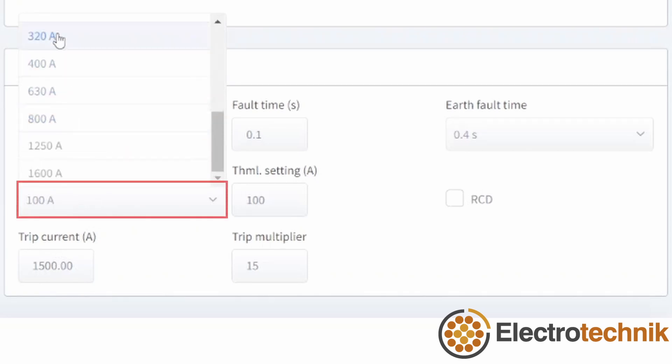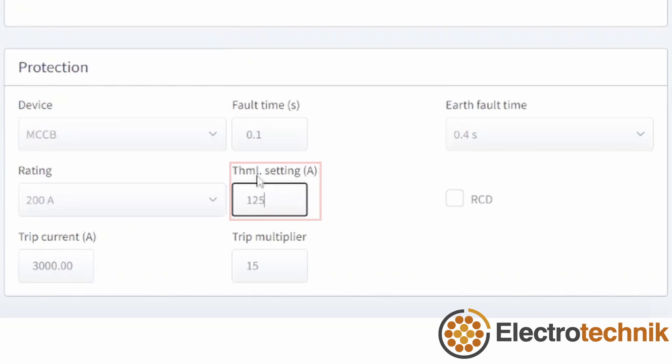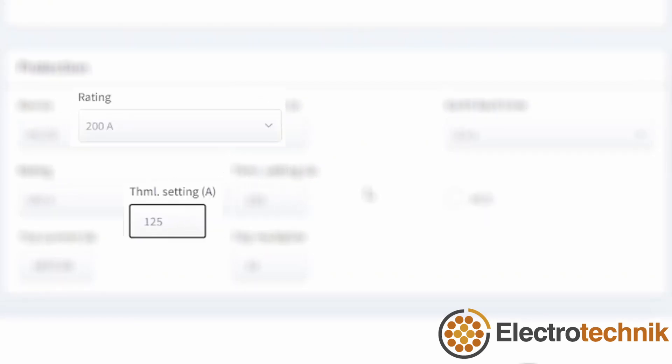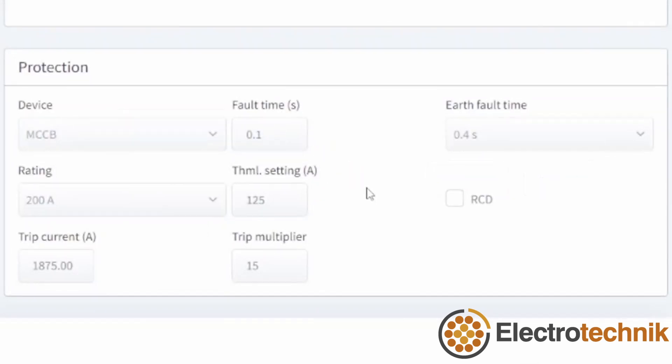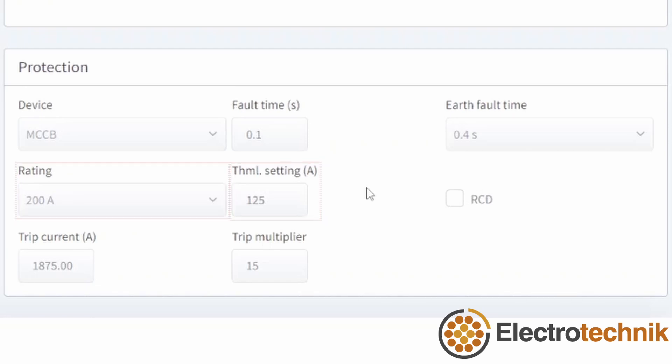For an adjustable device like the MCCB, the rating is the nominal trip rating and thermal setting is the actual current trip setting of the device, which should be less than or equal to the trip rating. The rating or thermal setting of the selected device must be greater than the load current in order to be able to properly protect the cable. The rating or thermal setting will also be used to calculate the minimum cable current rating.